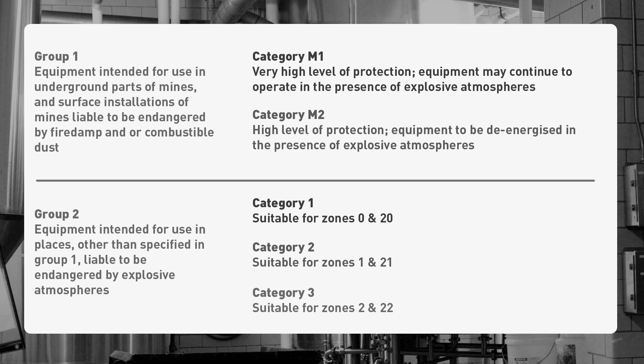Equipment intended for use in ATEX environments is split into two groups and five categories depending upon the level of protection required. Group 1 equipment is intended for use in underground parts of mines and surface installations of mines liable to be endangered by fire damp and/or combustible dust. Within Group 1, there are two equipment categories: Category M1, where the equipment must be able to operate safely even in the presence of explosive atmospheres, and Category M2, where the equipment needs to be de-energised in the presence of explosive atmospheres.